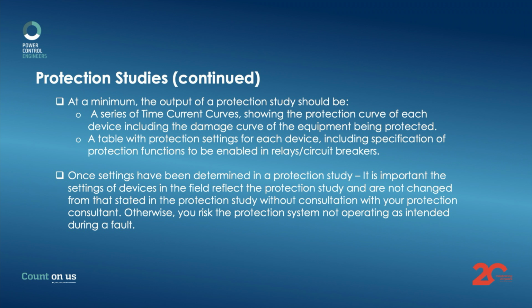Once settings have been determined in a protection study, it's important that the settings of the devices in the field reflect the protection study and are not changed from that stated in the protection study without consultation with your protection consultant. Otherwise, really, you risk the protection system not operating as intended during a fault.